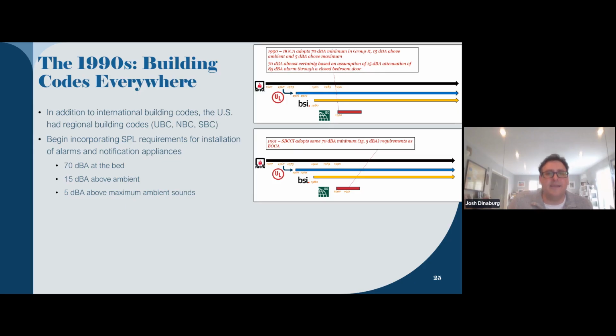So end of 99, we're starting to look at the 2000s. You get this great event where the International Code Council creates the IBC and consolidates all these different building codes, but they don't really change any of the requirements here - we're still looking at 70 dBA. 72 at this time gets rid of that exception that used to exist, so devices that went in a bedroom used to be allowed to be 75 instead of 85 dBA, but this requirement goes away in 1999.